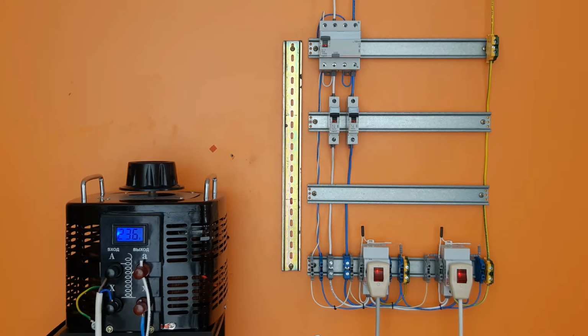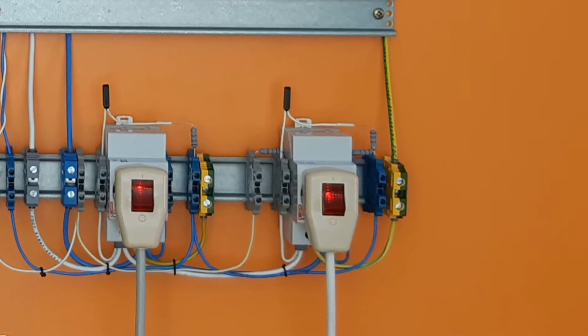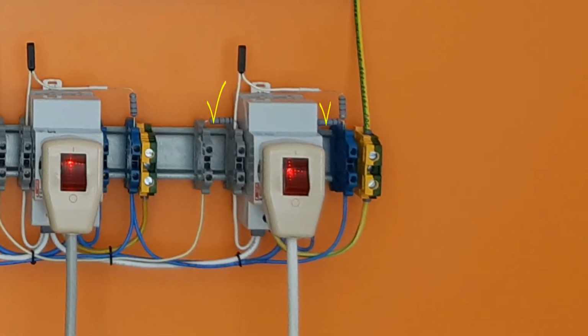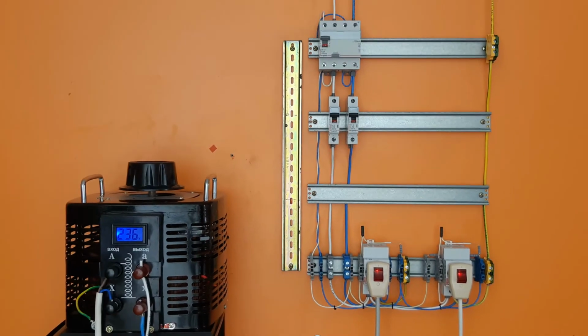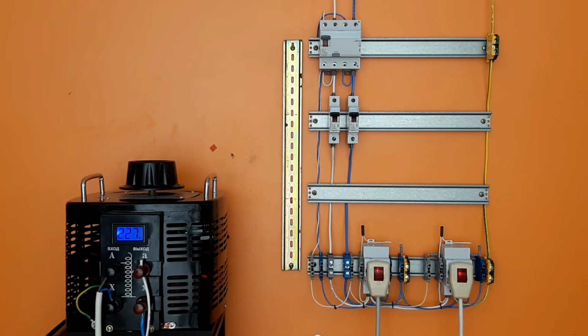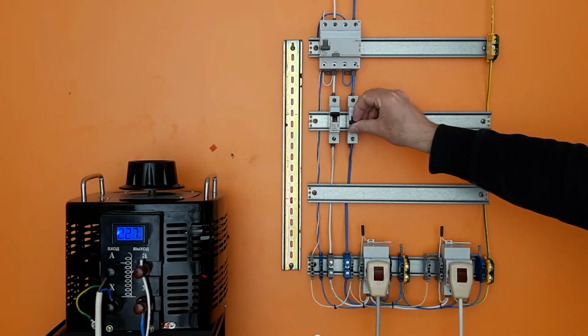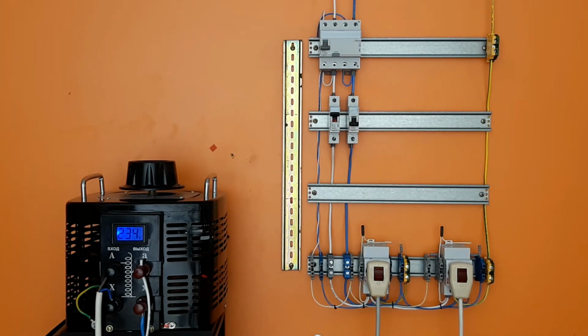For the organization of control, the free terminals of the dipoles are connected to the terminals of the same name of the extreme outlet through auxiliary resistors. Thus, the loop is covered by auxiliary conductors along its entire length. In the first experiment, we simulate the breakage of conductors. We turn on the device under load. By using an automatic circuit breaker, we interrupt the zero working conductor. The device is activated immediately. Complete power shutoff is provided.